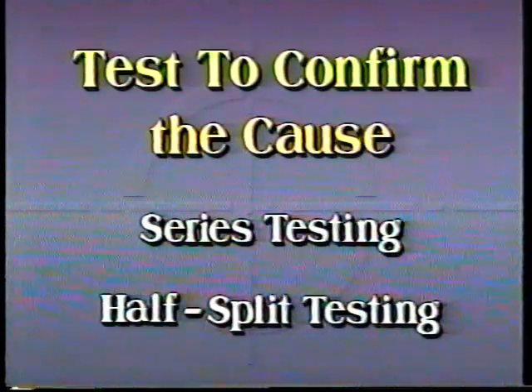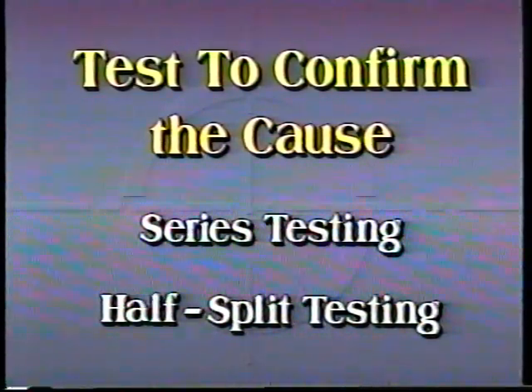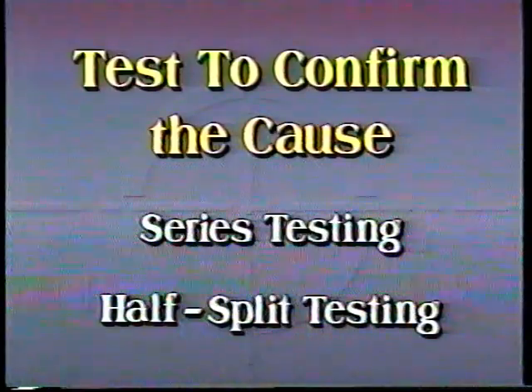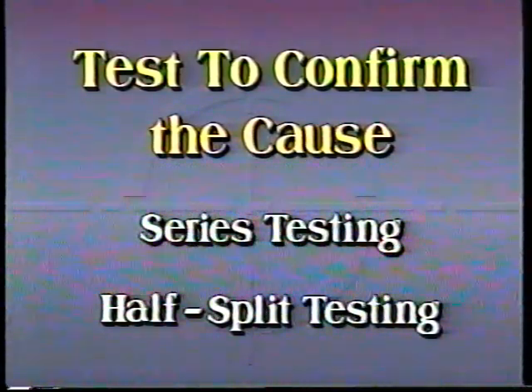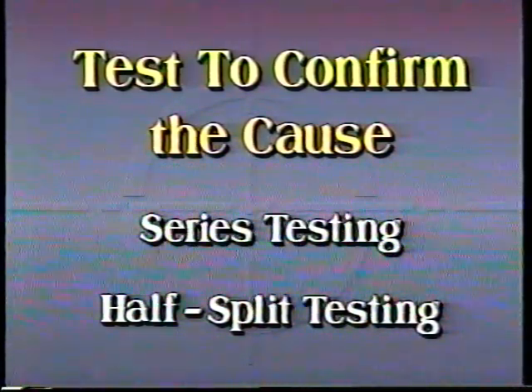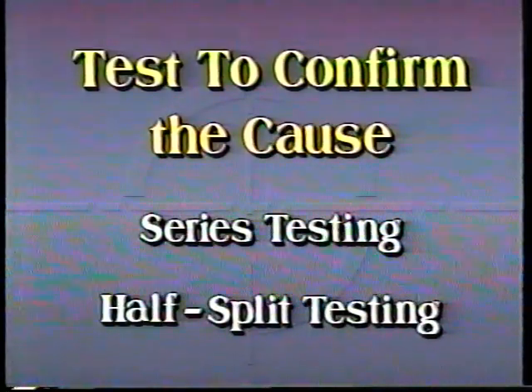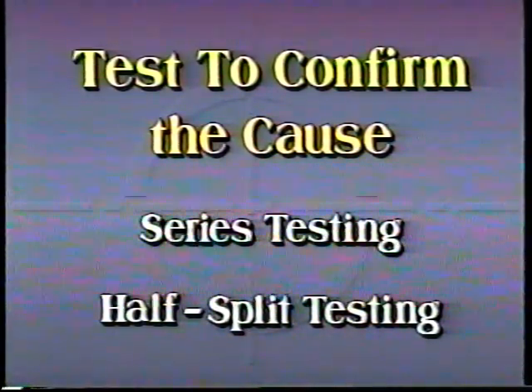In those situations where several possible causes may be the source of the problem, you should proceed to test in one of two ways: the series method or the half-split method. Most of the time, when you're troubleshooting mechanical problems, you'll use the series method. This is especially true if you have only a few possible causes. Series testing simply means that you will test one possible cause after another until one of them is confirmed as the direct cause of the problem.